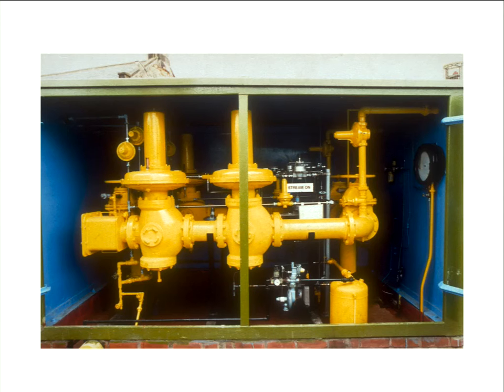Well, at distribution, they'll look at the coldest 6 minutes at peak in the winter. As you start to come back up the system, it might be the coldest hour, the peak hour. On the big transmission systems, I'll look at the peak day, and it should be able to cope with it. If it can cope with the peak day, it should be able to cope with anything below that. But then this one might be set at 2.1, so if this goes open, then this one comes into control a little bit higher.